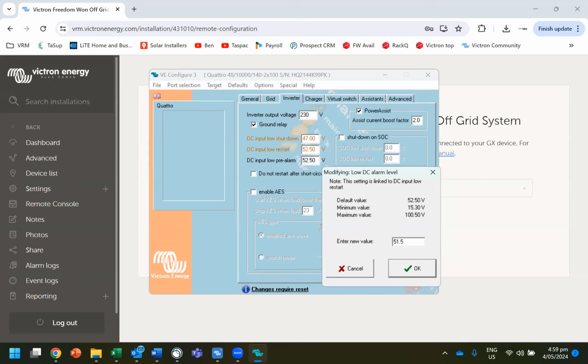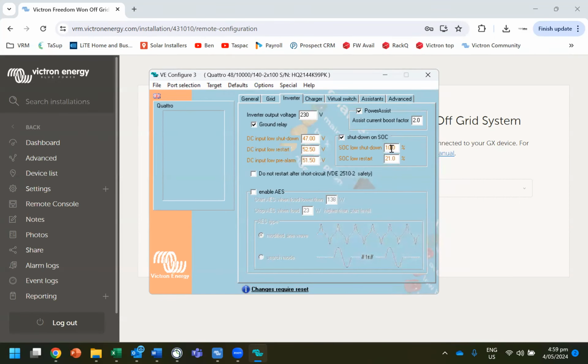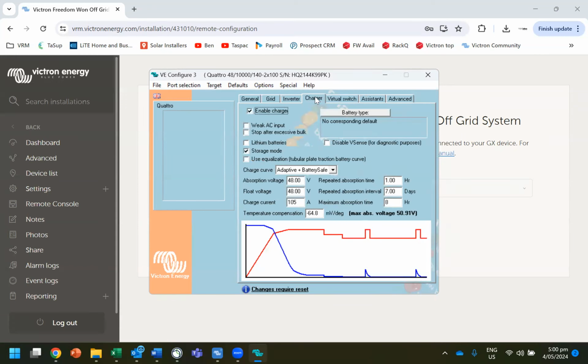So the inverter will show a little pre-alarm saying we're getting low and the battery's starting to get low and we're in trouble. You may also want to tell it to shut down and restart. So the restart value here, we'll say 21%, and we will shut it down at 20%. This means the inverter will turn off at 20% state of charge, then it will wait for the battery to start getting charged the next day, and when it gets to 21%, it'll turn back on again.